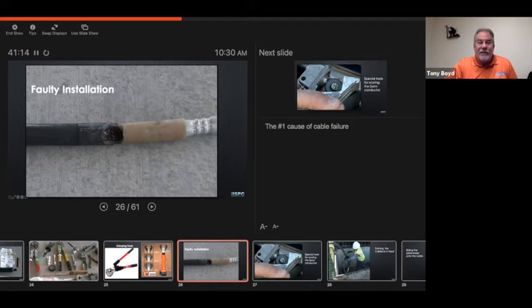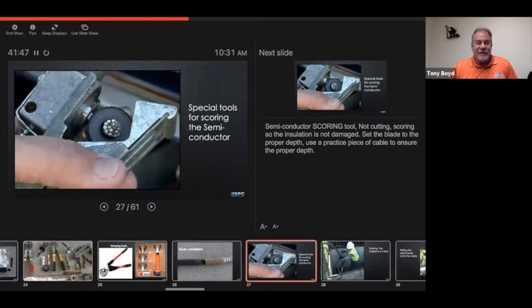One year later, we've actually put a little bit of load on this cable. So as we increase the amperage, we get leakage current coming through to that one little nick right there, and it blew out. And so it actually tracked down to the concentric wires that were back here. So I like to show this picture just to show that the simplest little nick can create a problem. So the number one cause of cable failure is faulty installation. And that's always a test question.